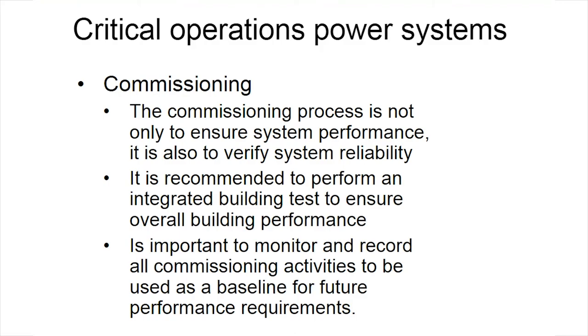Commissioning. Many times the commissioning for facilities is just to prove performance of the system, but when you're doing a COP facility, your commissioning is not just to prove performance, it's to ensure reliability. So you've got to sit down with your client and the people you're working with and ensure that whenever they prepare the commissioning plan, reliability is considered. That's really important. It's also important on this kind of facility to record all the activities, so you can use that to troubleshoot in the future and as a baseline to see what happened when an event occurred.